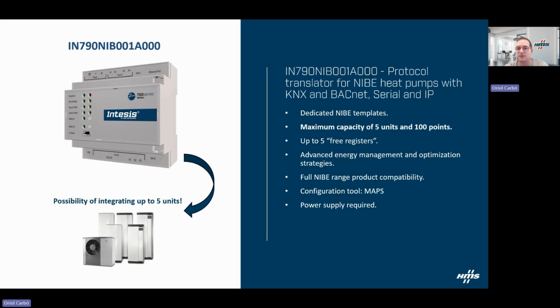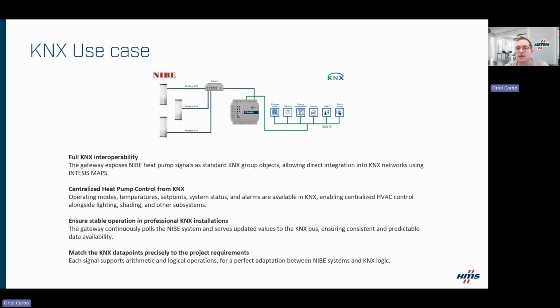The capacity is up to 5 units and 100 points, and a power supply is required. It combines wide NIBE heat pump compatibility with tools for energy monitoring and optimization. From the KNX perspective, the protocol translator exposes NIBE heat pump signals as standard KNX group objects using MAPS. This enables centralized heat pump control from KNX, including modes, temperatures, set points, and system status alarms, integrated with lighting, shading, and the rest. And the protocol translator continuously polls NIBE and updates KNX values for stable, predictable installations.